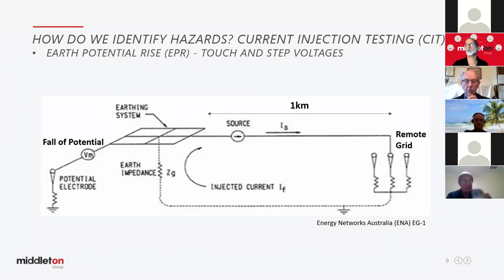However, it's quite difficult at times to get a transmission line out of service just for this test because of grid stability. So quite often we do what we call a remote grid test. We literally put a kilometre of line out. We find a nice area where we can put a couple of stakes in the ground and build a little grid. We can push current in the ground a kilometre away from the zone sub, and all that current we push out has to complete the circuit. It'll come back in through the grid and put current through the impedance. You can see there, the earth impedance, any current through that is going to generate a voltage that we can measure.